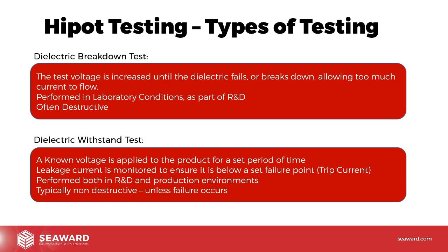And that's why we would never use this on a production line. We don't want to have the product in a less safe state than it was at the point it was built. So typically, the dielectric breakdown test is performed in laboratory conditions or as part of the R&D, where we only really want to understand exactly where the full breakdown point is. The more common test, the one that we'll talk about today, is the dielectric withstand test.